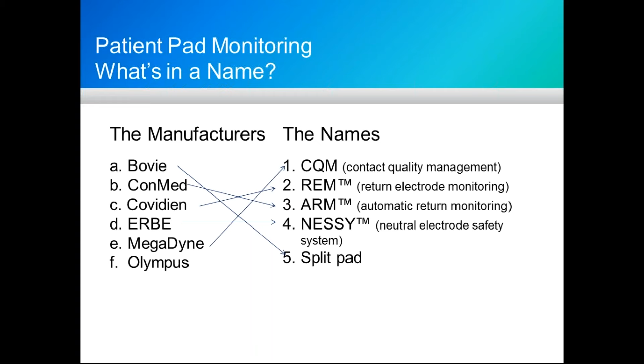For the first triad, you want to go through it to verify the REM circuit. The basic requirements are the REM plug, the REM cabling with the white tab on it, and some sort of tester, a decade box or a Unitherm. When you test it, it must be in the clinical mode, not in the demo mode. And you allow 2 seconds between the testing settings for the unit to settle.